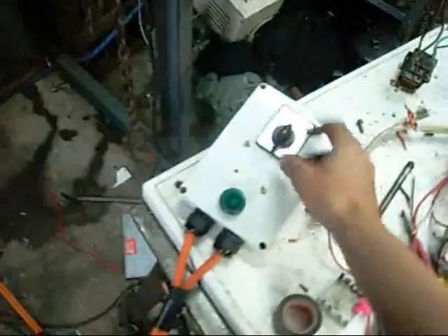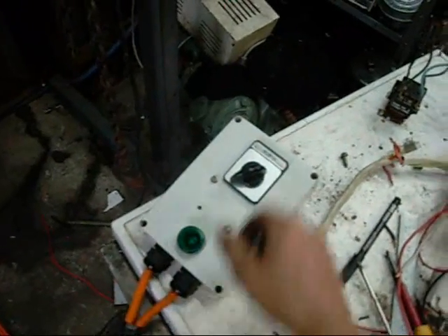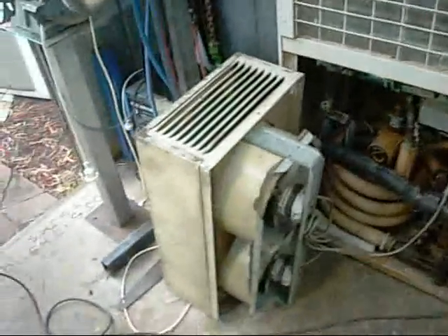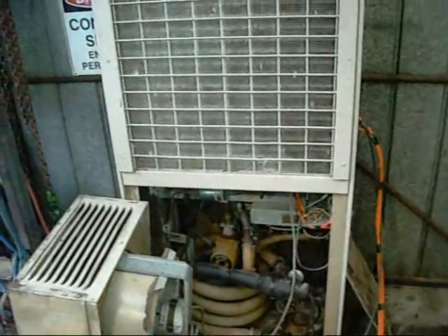There's one of those giant run capacitors in there too. I'm going to make that light work when it goes to fan and pump mode, make the fan work when I put it on fan and pump, and put the housing on this thing. Then I'll be able to hook up some water, hook up the indoor coil, rake some of that foamy crap off the coil, and just see what happens — see if I can find any leaks.